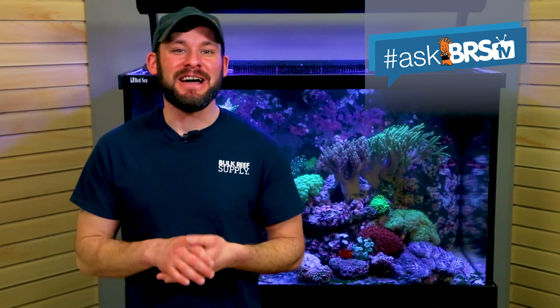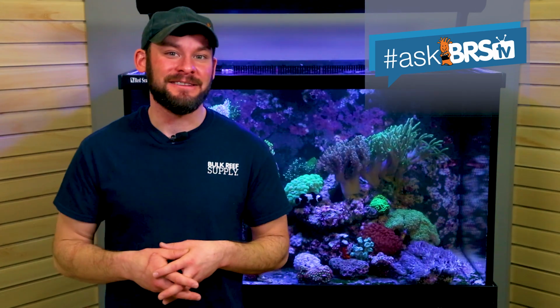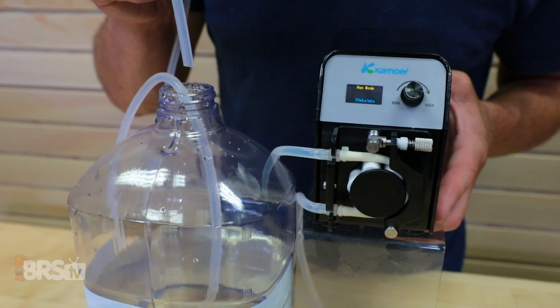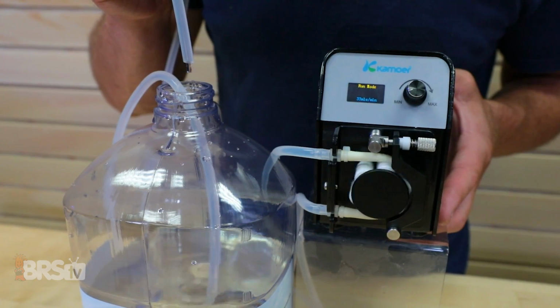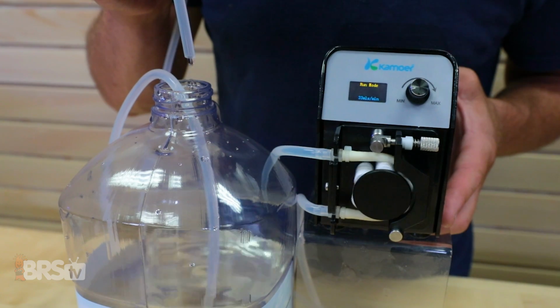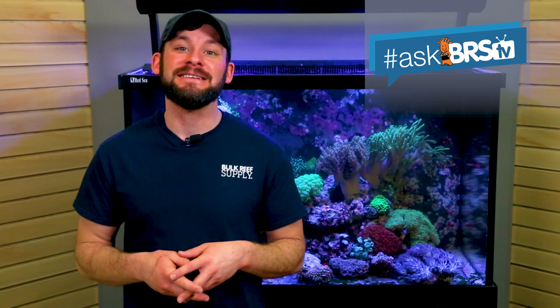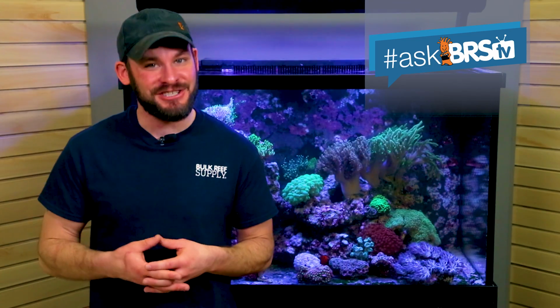To close this one out, I would again recommend recalibrating the Kamoer pump after changing either the tube or the pump head, along with semi-regular calibrations, not only to ensure it's consistently dosing accurately, but also to help you identify when it may be time for the next change.